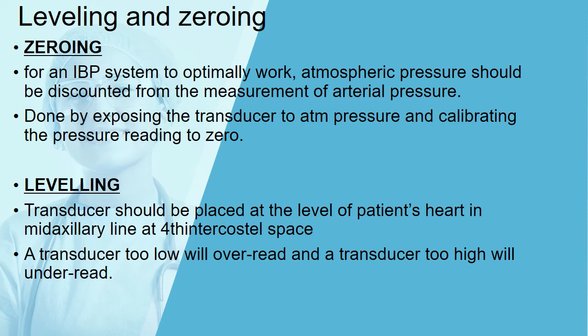Zeroing: for an invasive blood pressure system to work optimally, atmospheric pressure must be discounted from the measurement. This is done by exposing the transducer to atmospheric pressure and calibrating the pressure reading to zero on the monitor. Leveling: the transducer should be placed at the level of the patient's heart — at the mid-axillary line at the fourth intercostal space — in any position whether supine, prone, or head-up. A transducer placed too low will over-read, and one placed too high will under-read the blood pressure.